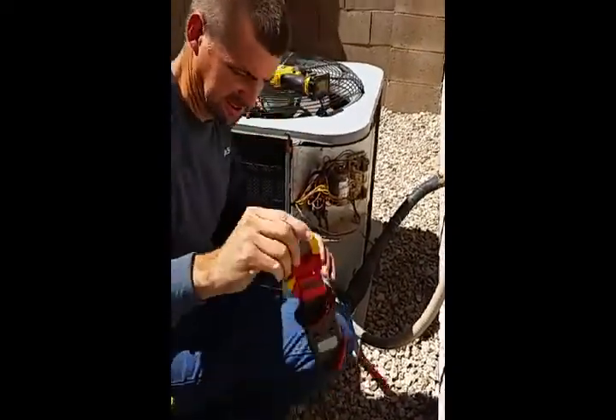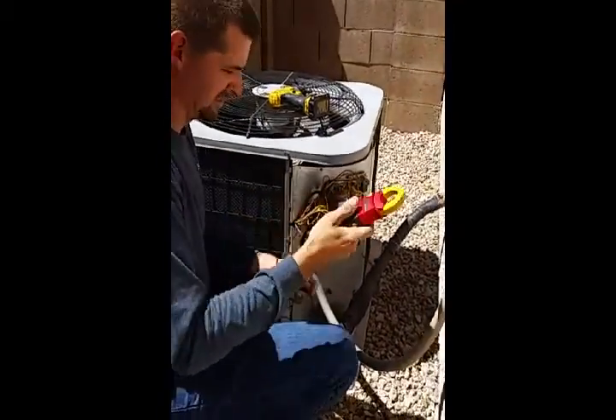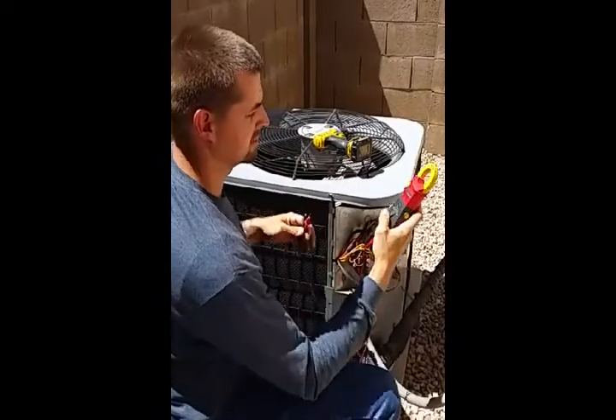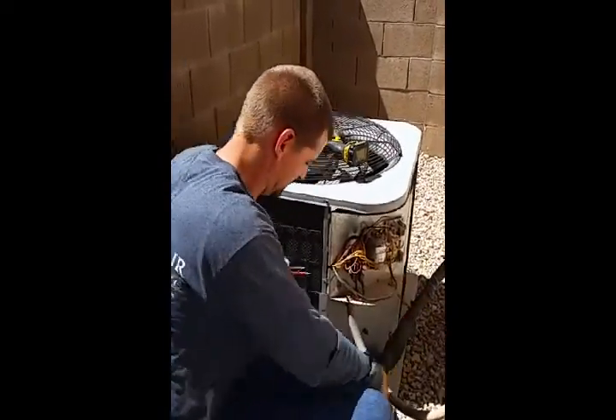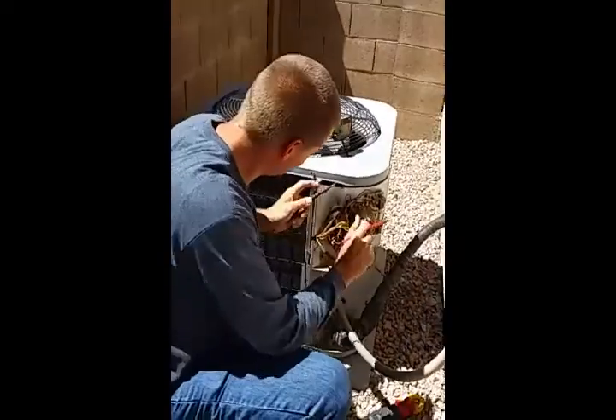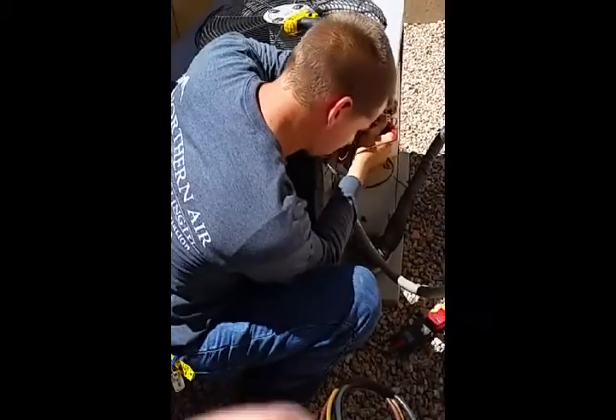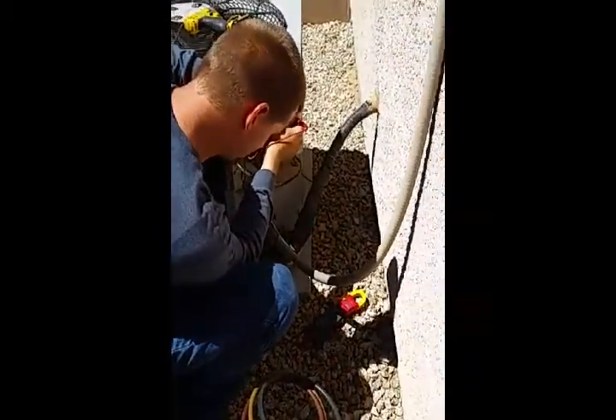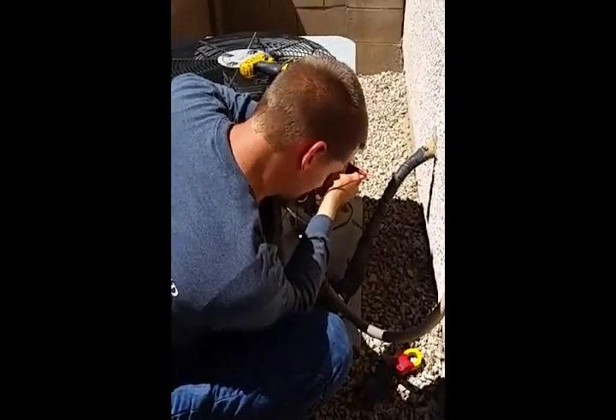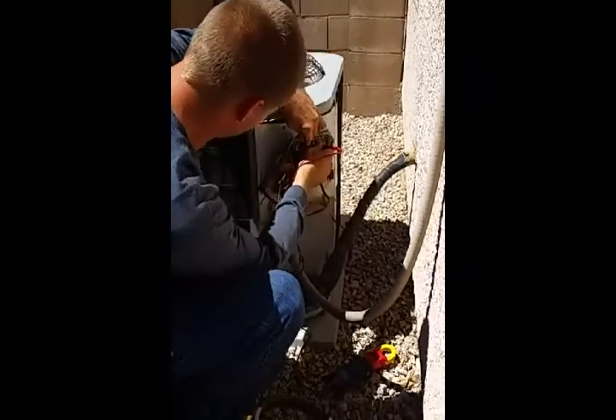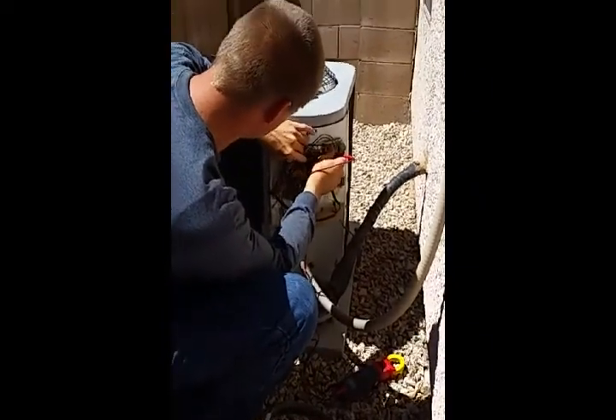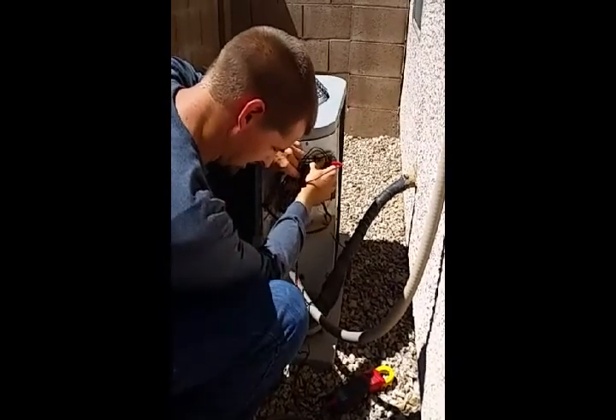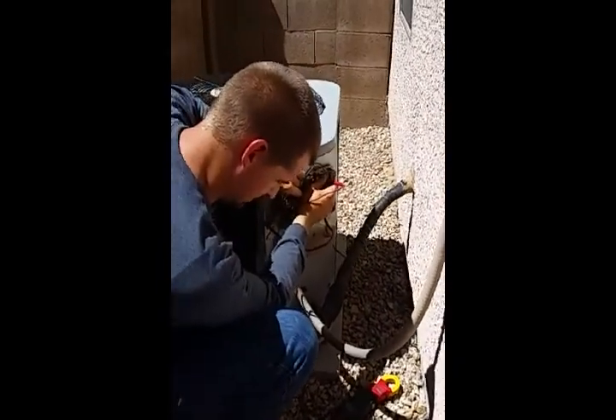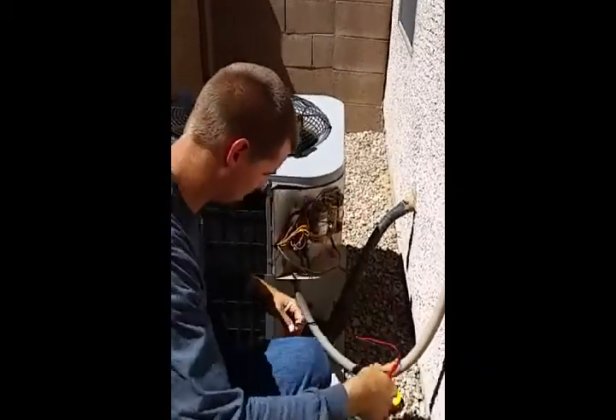Okay, now this is a 60 by 5 dual run capacitor. And we will test out the fan side. And we've got 5 exactly, so that is good. Okay, now we'll test out the capacitor side, or the compressor side, sorry. And that too is okay. So, go ahead and put everything back together.